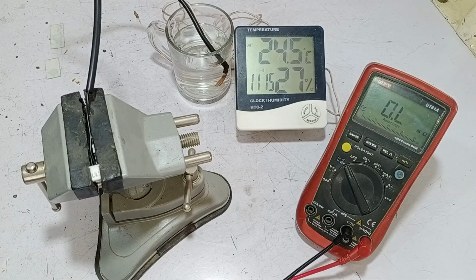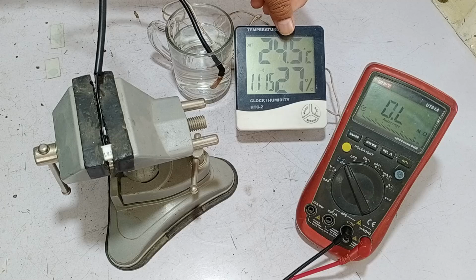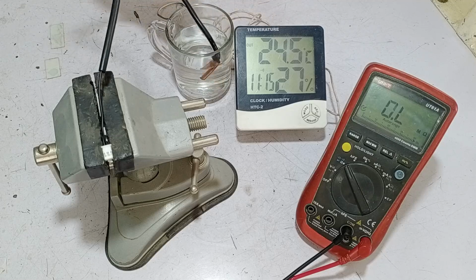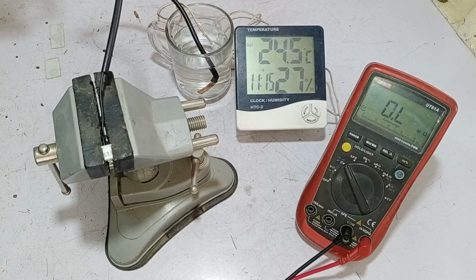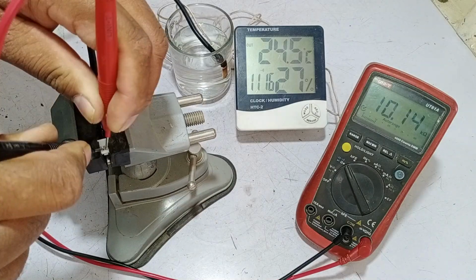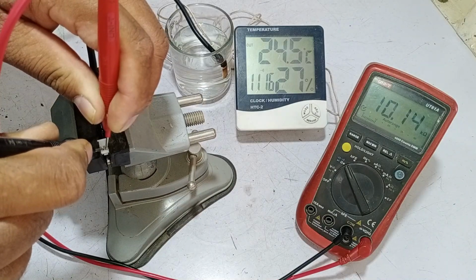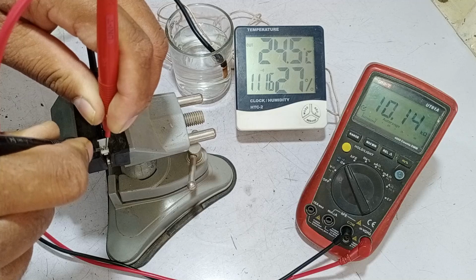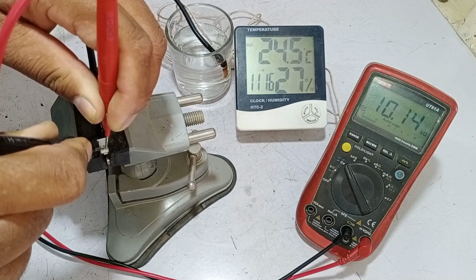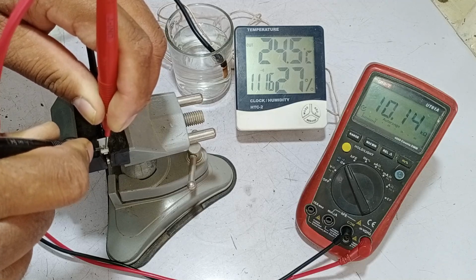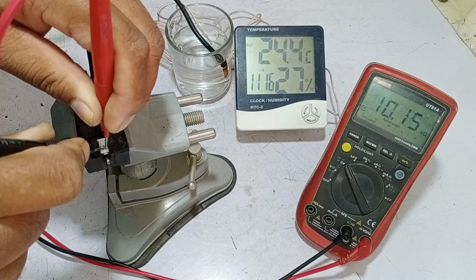Let's now talk about the value it should have. Currently, the temperature is 24.5 degrees, which is approximately close to 25 degrees. When its value was checked, it showed 10.14 kiloohms at 25 degrees. If this is the fixed value, then the sensor is perfectly fine. However, if the value fluctuates, it means the sensor is faulty. In that case, replacing the sensor will resolve the error.